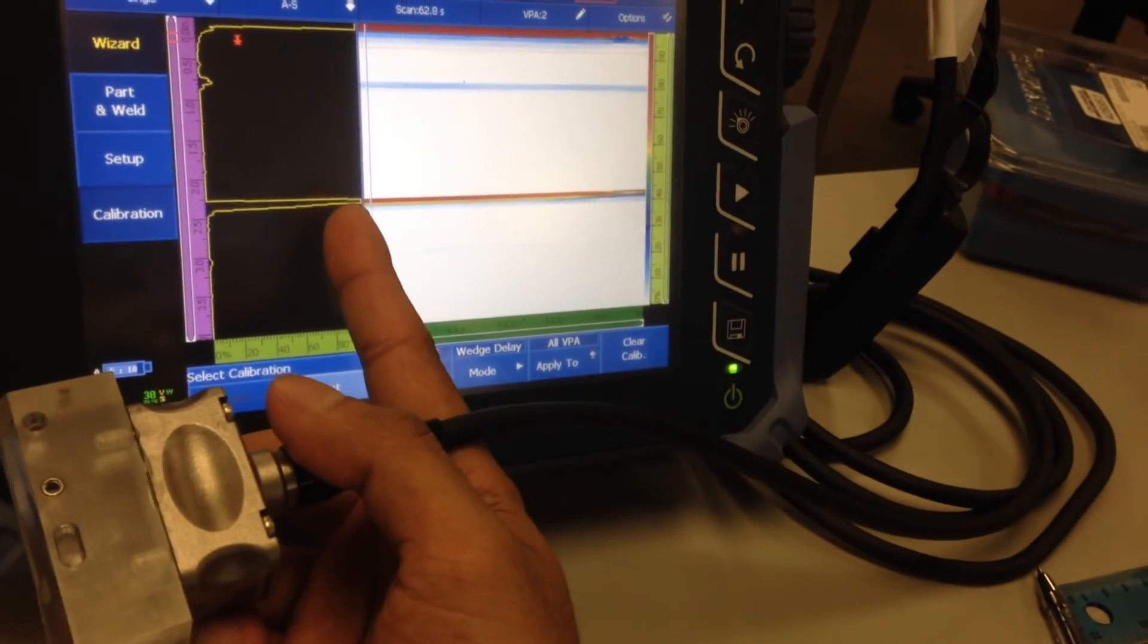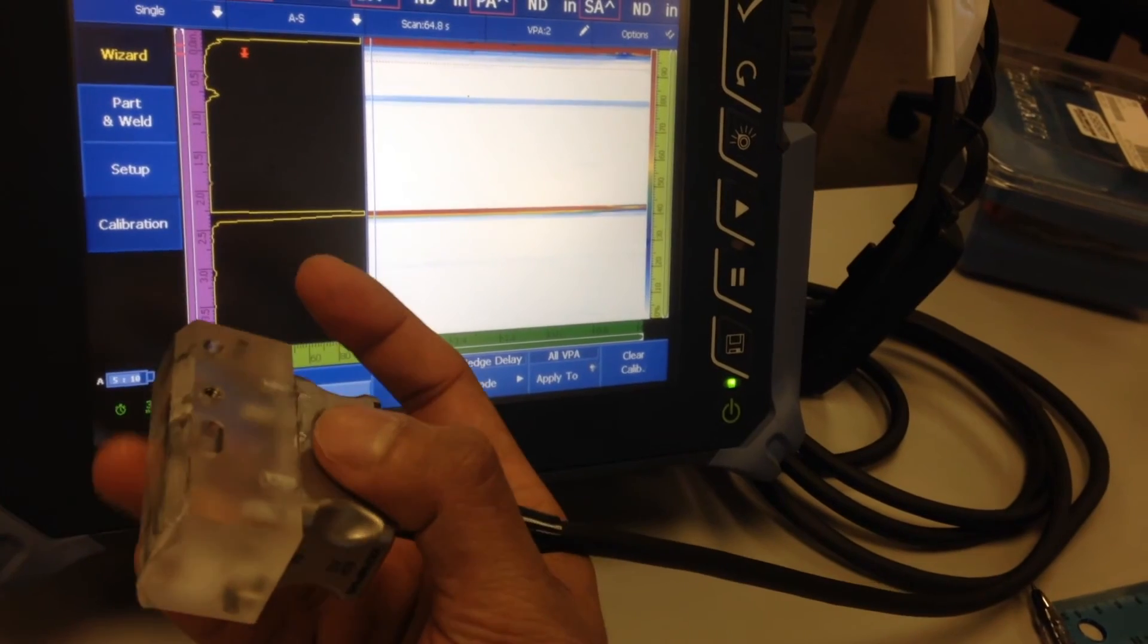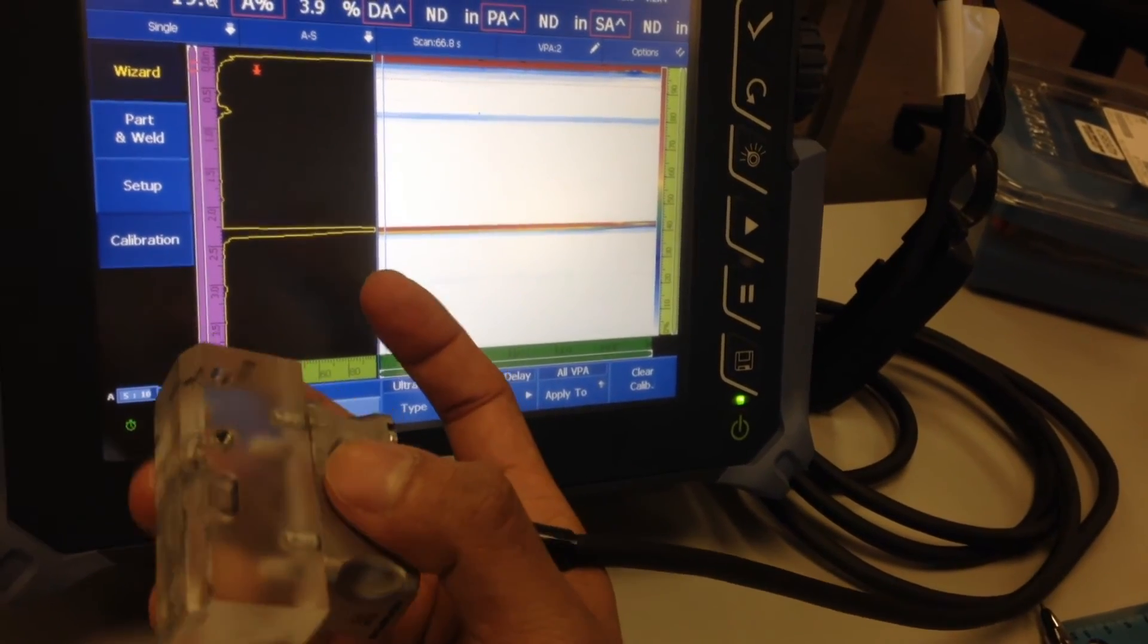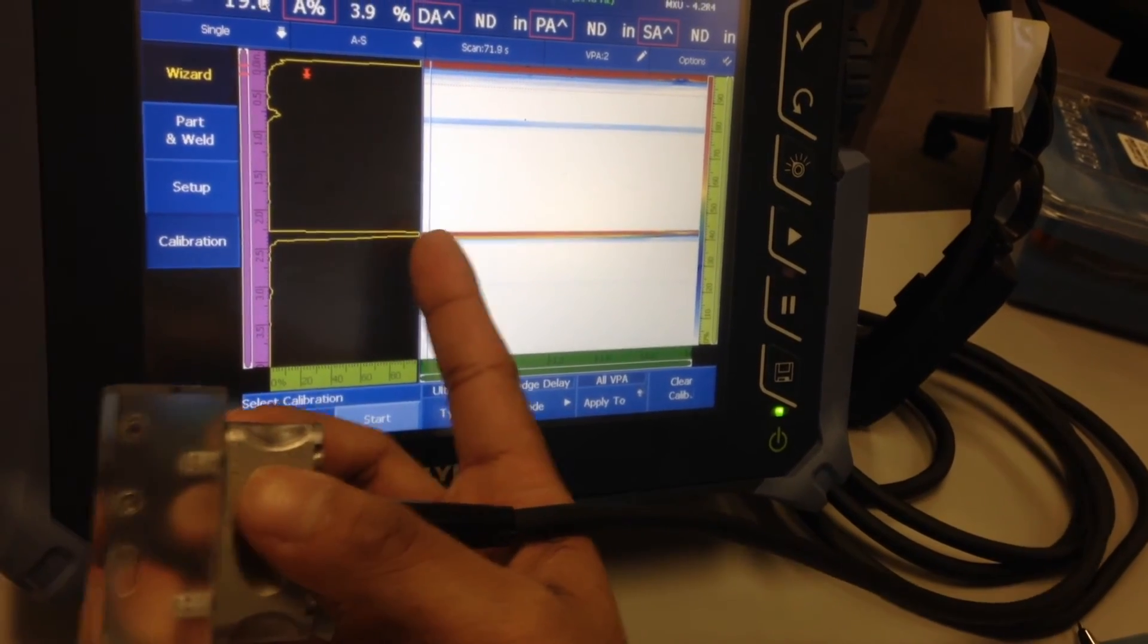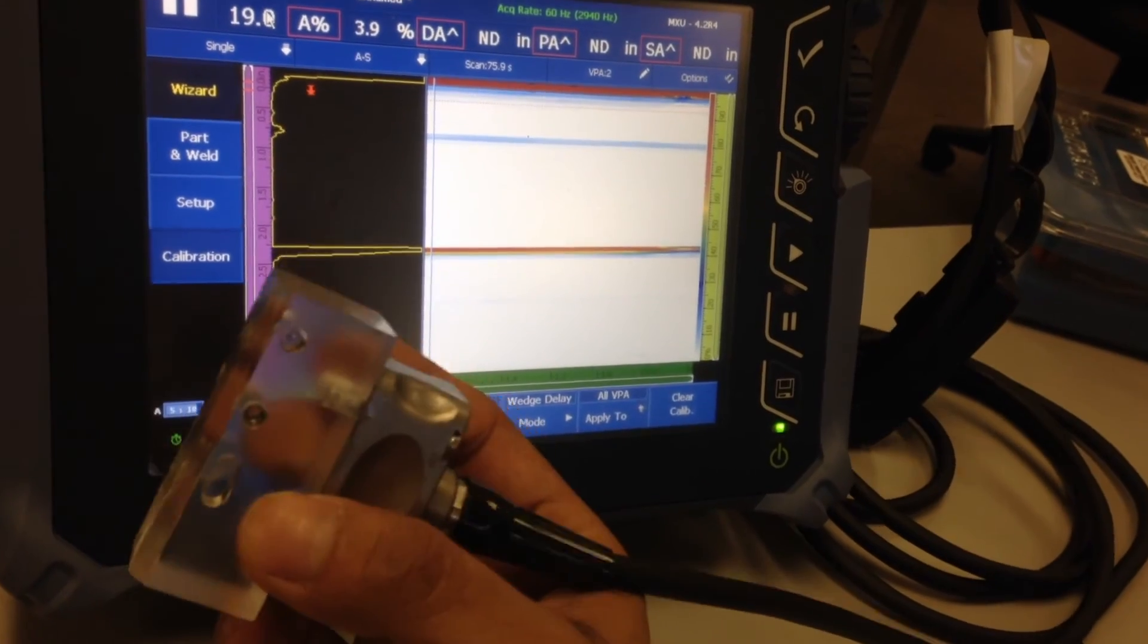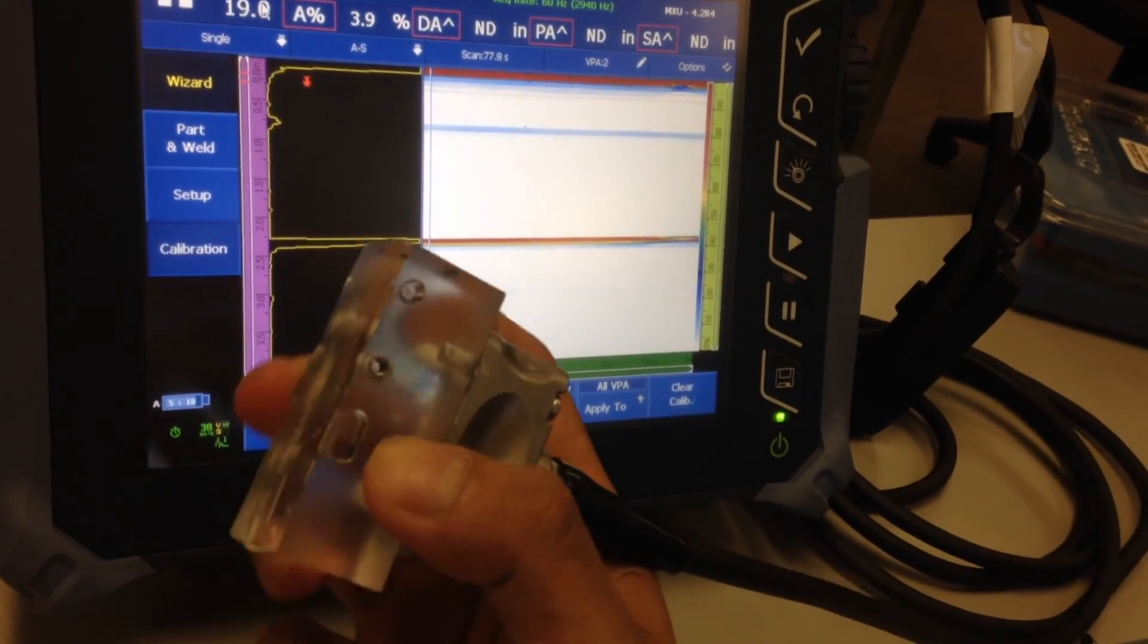Now don't confuse that signal with the second back wall. If you are confused which one's the back wall, just take your probe and wedge off of the calibration block and watch the screen for the signal that stays on the screen. So the one that stays is actually the signal coming off of the wedge and air interface. It's bouncing off of the wedge thickness, so that signal will always stay there in a zero-degree inspection with a wedge on. Don't confuse that with the back wall.